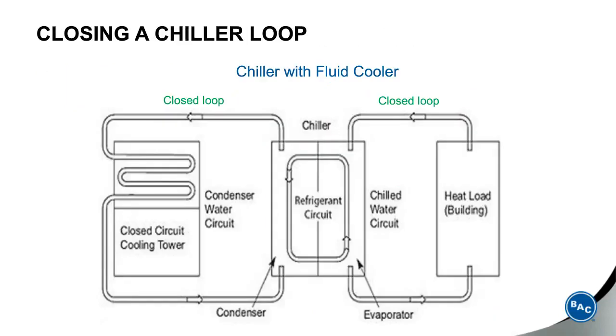Now let's look at closing a chiller loop with a fluid cooler. Here we have the same closed loop chilled water system on the evaporator side of the chiller, but on the condenser side we have the closed loop, where the warm water from the condenser is pumped to a coil that is located in the closed circuit cooling tower, and water is sprayed from the sump of the unit up over the coil. Air is induced into the unit, and the evaporative heat transfer occurs on the surface of the coil, cooling the fluid within the coil. That water or glycol returns from the coil of the closed circuit tower back to the condenser to pick up more heat. But in this case, both sides are closed, both the chilled water side and the condenser side.